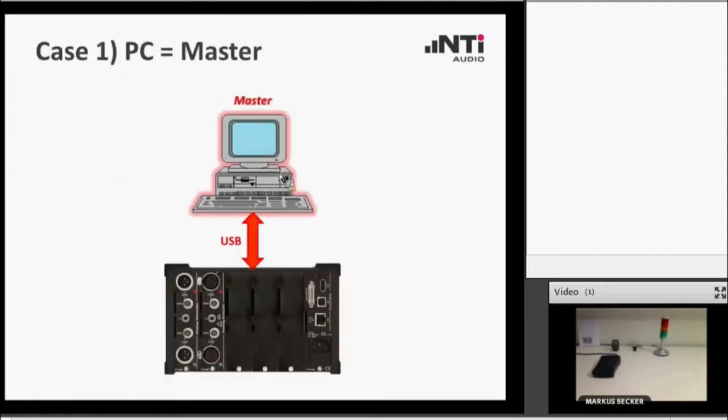So let us first take a look at the typical system settings of the Flexus audio analyzer. We start with a first typical setup, and we call it the standalone application, where the controller PC is the master of the system. That means that there is no external controller, no host controller, no external PLC that would drive the system. It's just the PC that is connected to the FX100 via the USB link. And this PC is the master of the system itself.